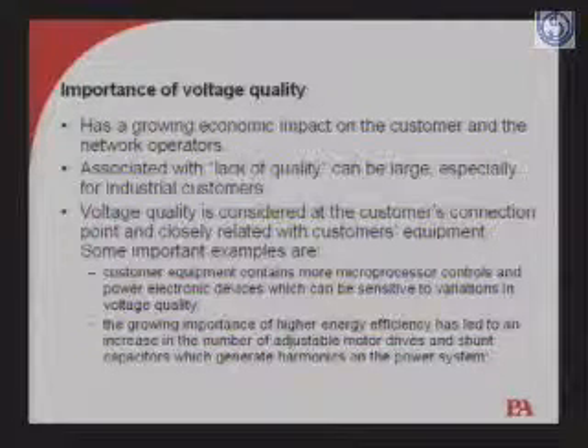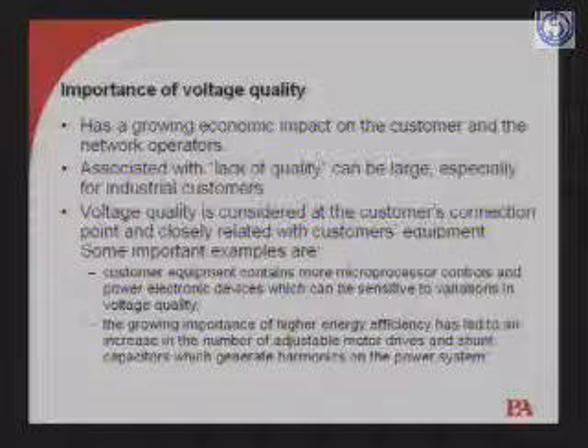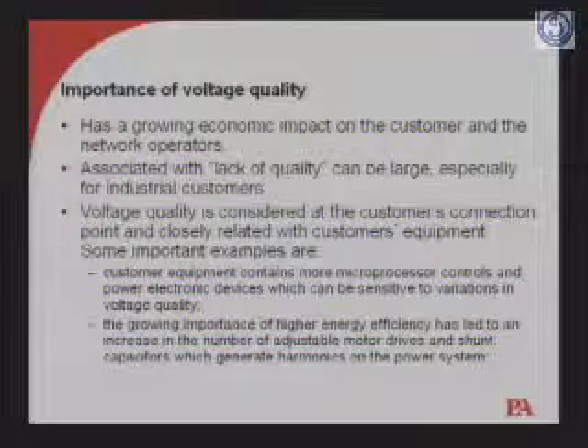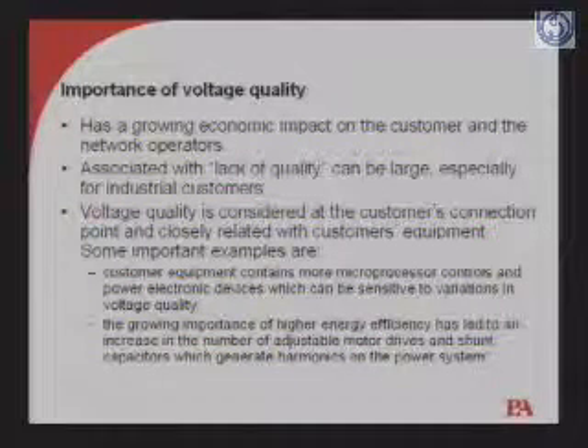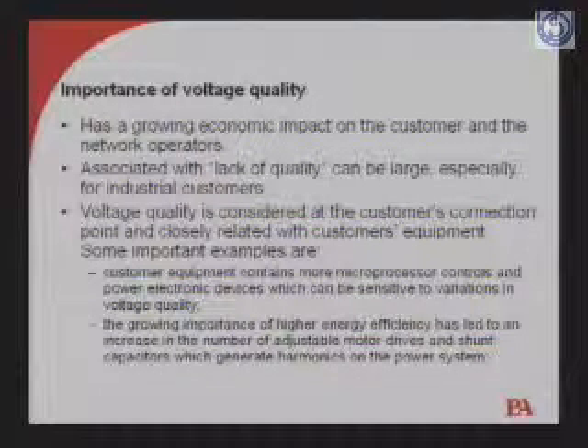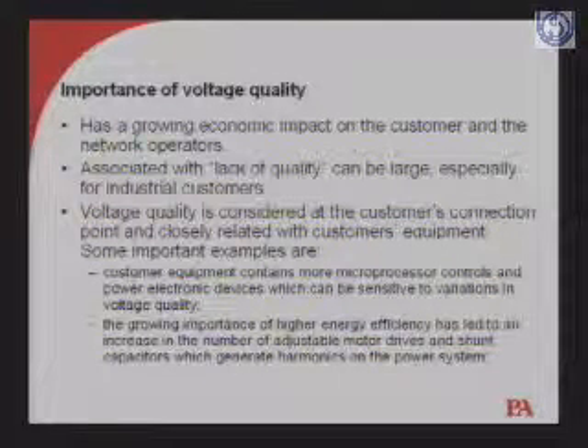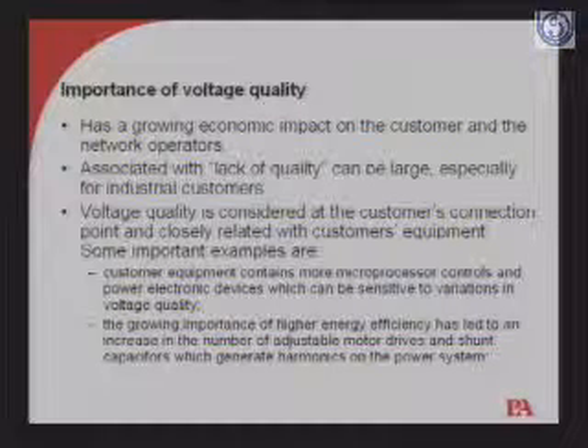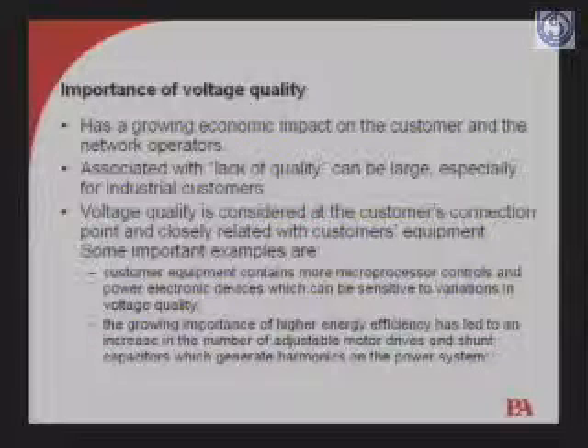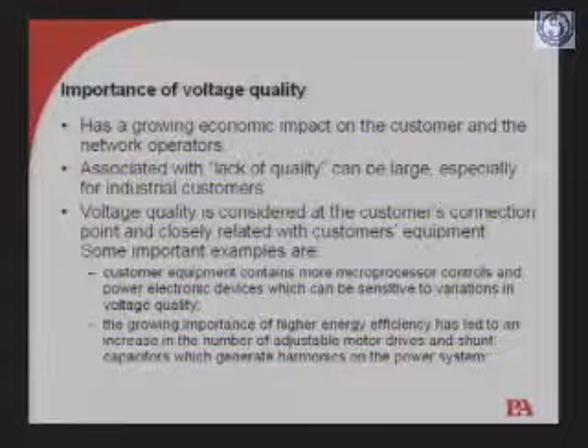The customer wants to save on electricity charges, so newer technologies are being applied. They require that their motor run at a predefined speed for a particular process for a predefined interval. For that purpose, they have speed controllers. They also need the proper power factor to reduce electricity consumption, so they use capacitors. All these are good, but they are also injecting harmonics into the system. Harmonics in turn distort the sinusoidal waveform. So the voltage quality is distorted.